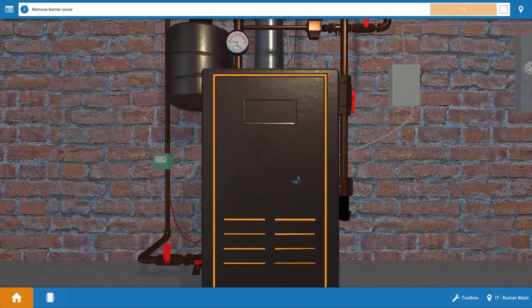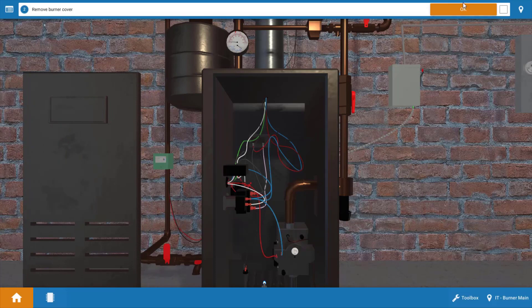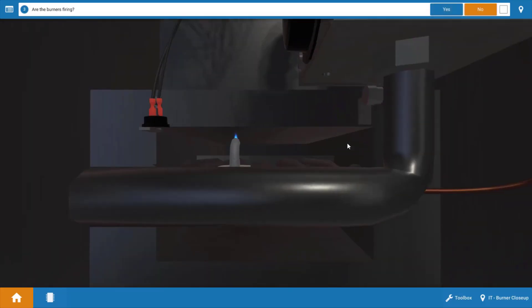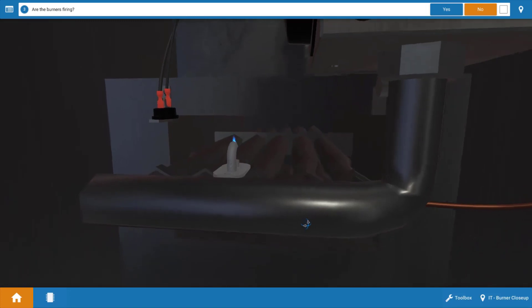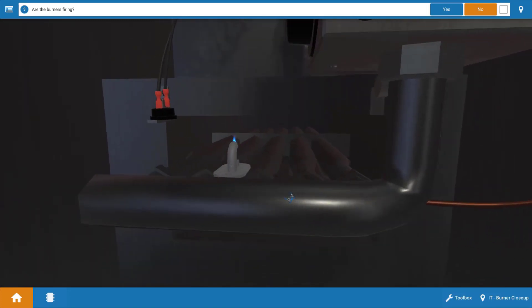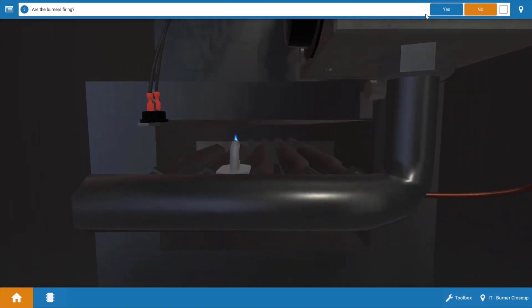Next, we're going to remove the burner cover and take a brief inventory of which components are running or operating. First, let's look at the burners. Well, we can see we don't have any burner operation here. We do have a pilot flame, but there's no burners lit, so we're going to click no.